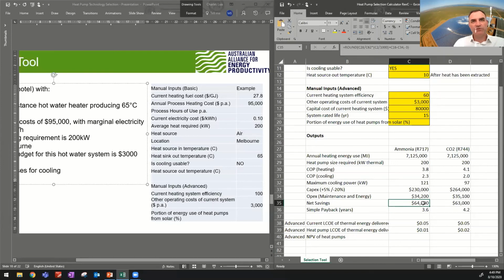Ben asks, would it be worth considering redundancy in your selection and capital cost pricing? A standby heat pump versus standby boiler may extend your payback. I think that would come down to taking a similar position to what you do with your chiller system, similar availability. Having a complete backup chiller system isn't always the case, but if that reliability is needed, it may be there. I'm not sure there's such a big difference if you're doing proper maintenance.